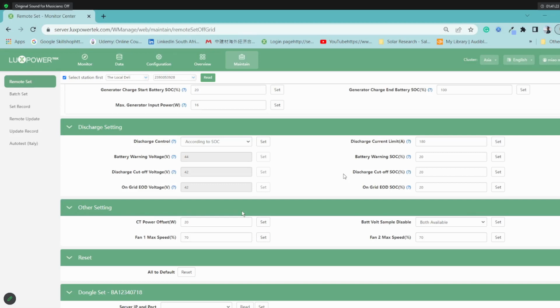So we just need to prioritize your PV input power. But also with the PV input power, let's say it's at a point now where it can produce like 3 kilowatts of power, but the household doesn't need that much. It only shows you how much it's using. So that's something else the client needs to understand. If your household load, combined with how much power needs to go towards charging the battery, is less than what the panels are producing, the panels only show you how much it's using.